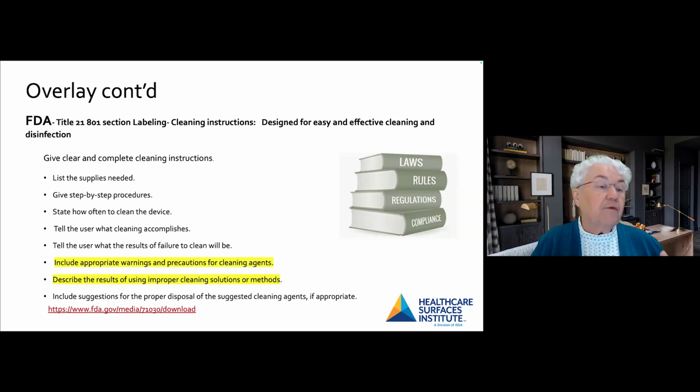So if the IFU is not followed the way it's presented by the manufacturer, then damage or other conditions may occur that may make that piece of equipment either not function properly or continue to get damaged by having these micro fissures, microorganisms come into play. And then it should also include suggestions for disposal of any of the cleaning agents if appropriate. It's got to be very complete.